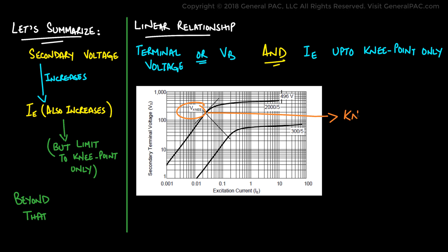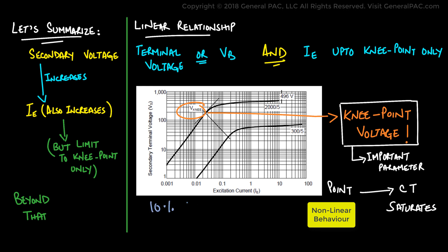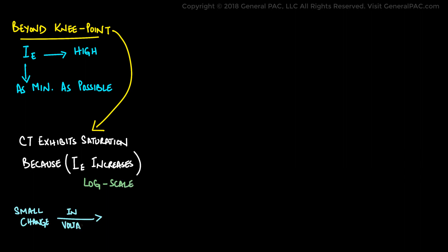This point is called the knee point voltage and is a very important parameter. It is the exact point where the CT starts to exhibit non-linear behaviors, where a 10% increase in the secondary voltage causes an increase of the exciting current by 50%. If we go above the knee point of the curve, the exciting current will be abnormally high. We must keep the exciting current as minimum as possible to avoid saturation. Anything above the knee point causes saturation, because a small change in voltage produces a huge change in current — the exciting current increases on a log scale.